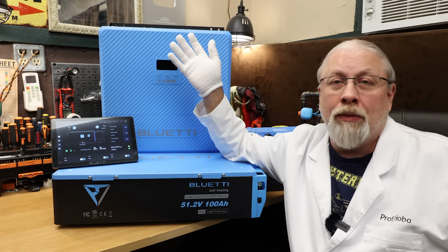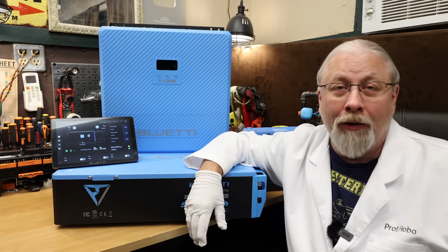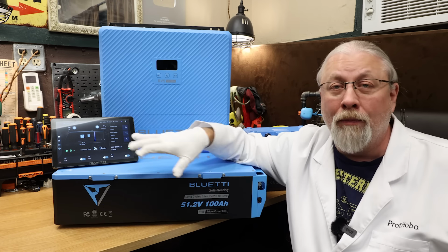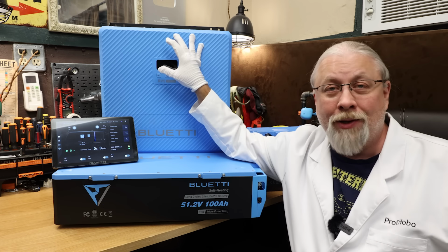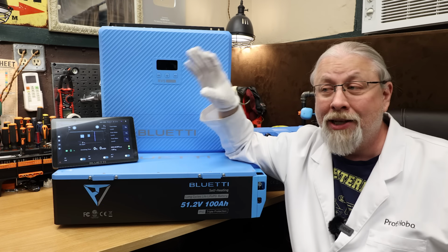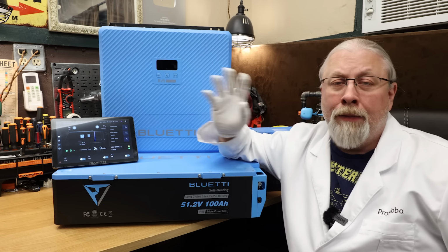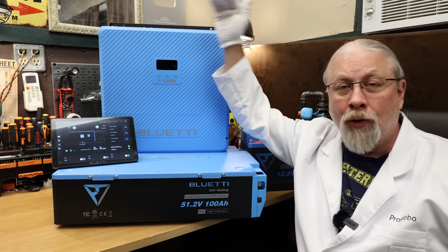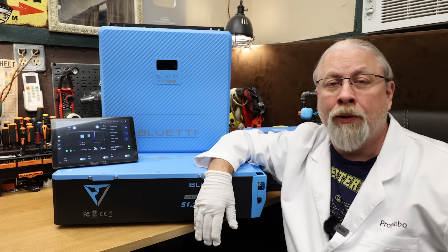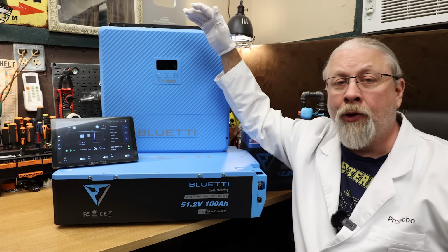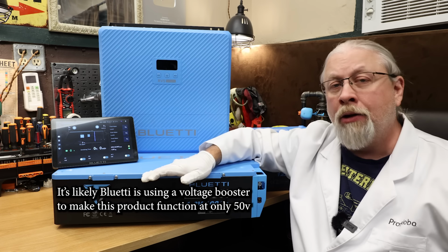Yes, every monkey on the planet knows panels in parallel are better for shading, but when you have a 50 volt battery bank and a 50 volt MPPT controller, you run into a serious problem: MPPT controllers thrive on higher voltage. In order for them to work properly and efficiently, you need a much higher voltage on the solar than the battery voltage.